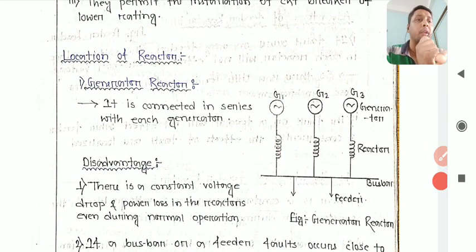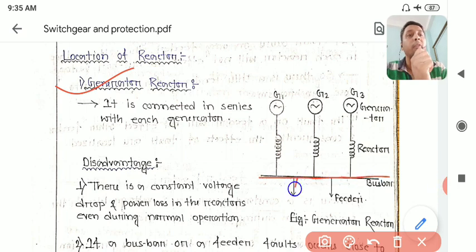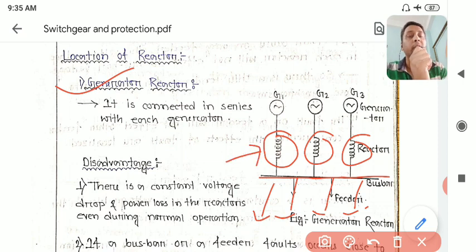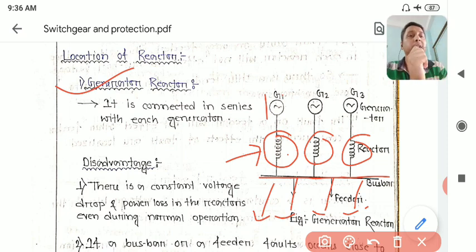There are different ways to place the reactors. The first method is generator reactors. In this method, the bus bar connects all the generators, and from here all the feeders go out. With each generator, one reactor is connected - this is extra reactance added in the line itself. This equipment, similar to a large transformer, is known as a reactor. It is connected in series with the generator so that it will be in series with the generator reactance when a fault occurs.